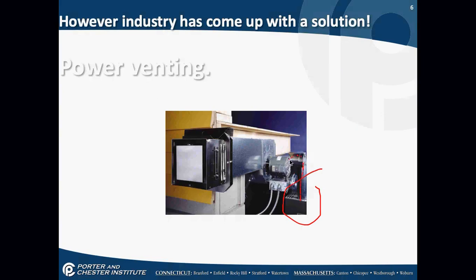Coming out of the furnace, we have our vent pipe, the exhaust pipe. It goes into a motorized power venter that pushes the air. It sucks from the furnace side and it pushes the air out a vent on the side of the house. That's a power venter. This power venter comes on as the first part of the ignition sequence. In other words, we can't even start the burner motor. We can't open an oil valve. We cannot start anything until this power venter is running.